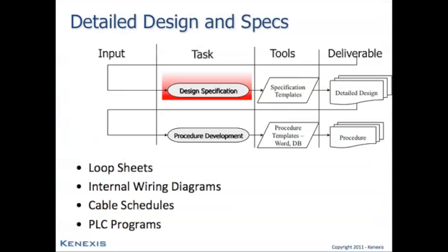After the conceptual design phase and after the verification of the safety availability of all of the FGS functions, the next step is to perform the detailed design and detailed specification of the FGS system. This step is not dramatically different from what has traditionally been done for fire and gas detection and suppression systems and for instrumentation and control systems in general. This would include the development of loop sheets, preparation of internal wiring diagrams, drawing of cable schedules, and also the development of PLC programs where programmable systems are used as the logic solvers for the FGS.